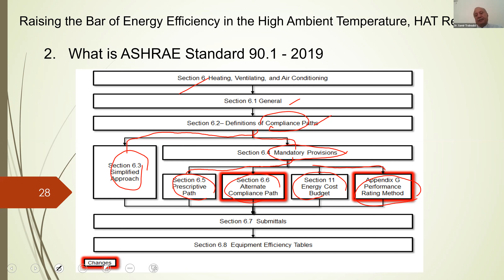The simplified approach has certain limitations: the building area should be less than or equal to 2,400 square meters, it should not exceed 1 or 2 stories, the system should have a single HVAC zone, and there are certain criteria available for the cooling and heating parts.